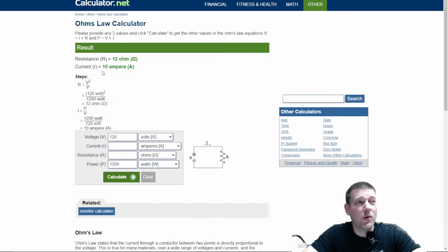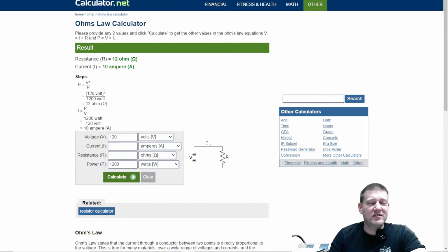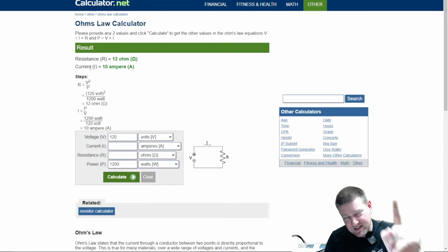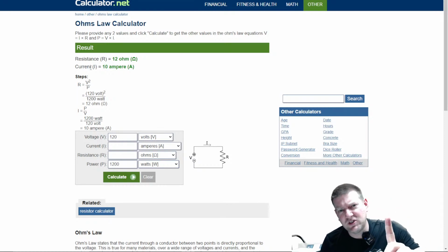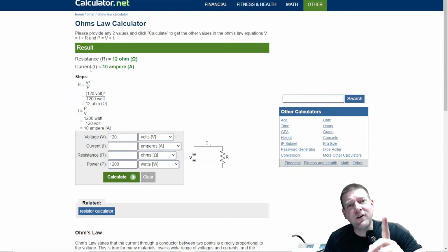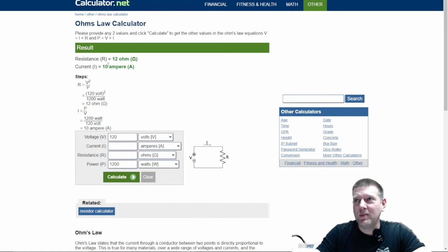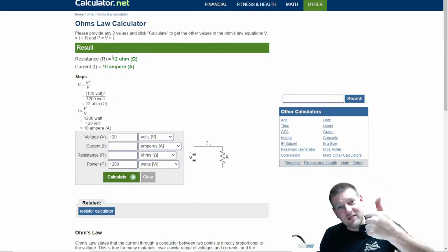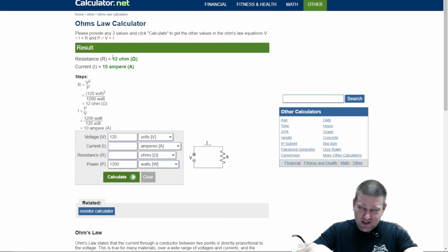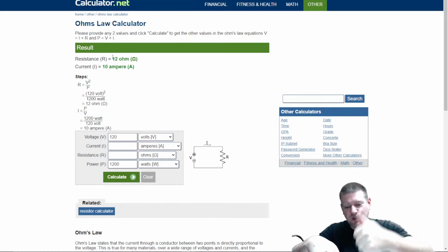Whew, what's going on? So this particular device right back here behind me, it starts out low, like 10, 11 amps, and then it goes all the way up to 15 or 16. Well, if the voltage stays the same, which it should be, unless you have some voltage sag, then the only other thing that's changing is your resistance, which means the heating element is actually dropping resistance in order to increase the current, because as you decrease resistance, the current is inversely proportional.